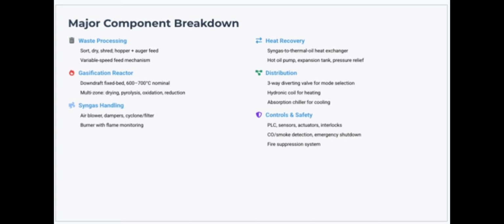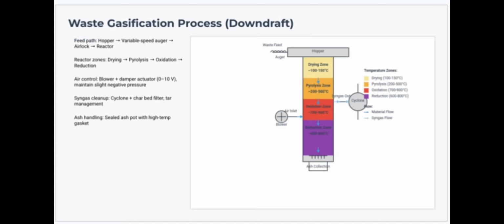reactor, downdraft, fixed bed, 600 to 700 degrees Celsius normal, multi-zone drying, pyrolysis, oxidation, and reduction. Syngas handling: air blower, dampers, cyclone filter, burner with flame monitoring. Heat recovery: syngas thermal oil heat exchanger, hot oil pump, expansion tank, pressure relief. The distribution: three-way diverting valve for mode selection, hydronic coil for heating, and absorption chiller for cooling. For controls, we will be using PLC, sensors, actuators, interlocks, CO/smoke detection, emergency shutdown, and fire suppression systems.